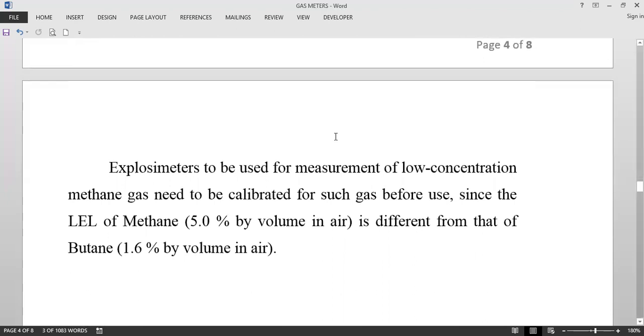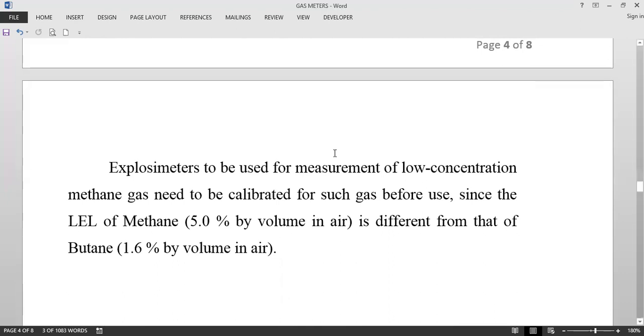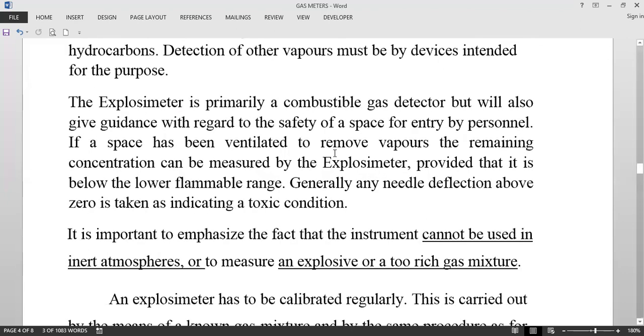Butane is suitable for calibration of explosimeters used for measurement of crude oil, as the vapors of this oil contain mainly butane and propane. Explosimeters to be used for measurement of low-concentration methane gas need to be calibrated for such gas before use, because the lower explosive limit of methane is higher — about 5% by volume in air — which is different from butane, which is only 1.6% by volume in air.